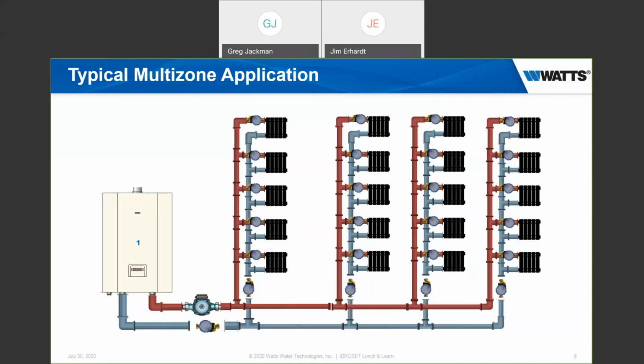So when we say balancing, it really is a balancing act to get all of these radiators and stacks properly tuned so that each heat emitter or radiator is getting the flow it needs to deliver the designed heating or cooling load. So in a brief 30,000 foot view, that is what we're up against when we're balancing. And that is why it's important that we do this process, to ensure that the system not only provides the comfort it was intended to provide, but also works in the most energy efficient way possible.